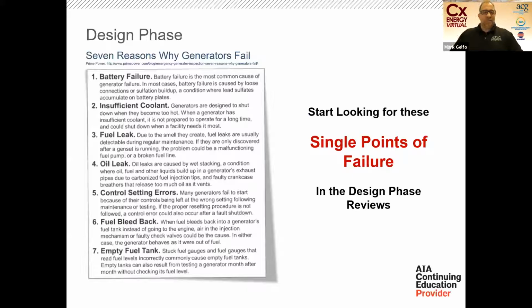Now that we're done with the definitions, we're going to start talking about design, construction, and commissioning. Our job is to look at those single points of failure, and we find there's a lot of commonality in why generators might fail, or in this case, why they don't start. 57% of you were right that battery issues are typically the reason generators don't start—there are lots of different reasons, but battery issues tend to be the biggest one.